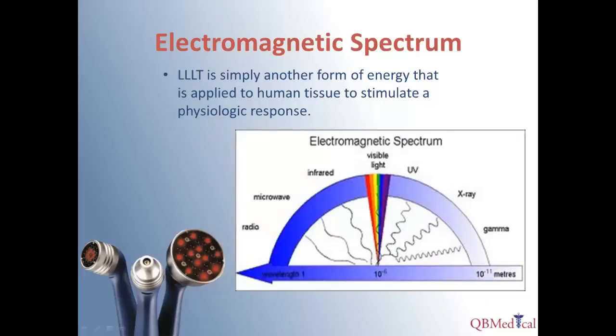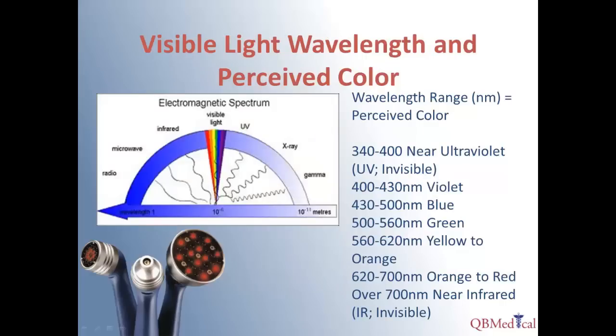Being monochromatic, each individual laser emits energy at a single wavelength or color on the electromagnetic spectrum. Using differing active lasing mediums will result in different wavelengths of light being produced, and this is important because different wavelengths have different penetration capabilities into tissue. Most cold lasers are in the red to infrared or near-infrared range, meaning they may be invisible to the human eye. Cold lasers typically have wavelengths of 600 nanometers and above.